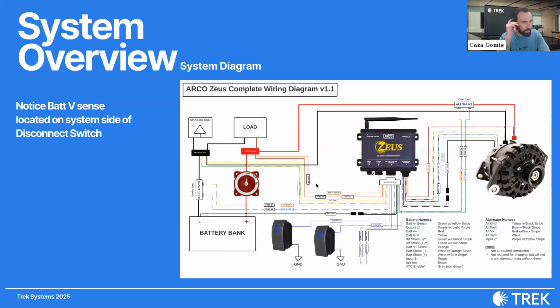Yeah, real quick, I'll jump in on that piece as well. That's very important, where you put the battery voltage sense - you don't want it to go directly on the battery, it needs to be on the system side. For those of you who use a Lynx distributor, it should be on the load side of the fuse as well, so that if that fuse ever blows... if we think about a Lynx distributor, the fuse has one side on the positive bus bar, the other side goes out to the alternator, or whatever our load or charger is.